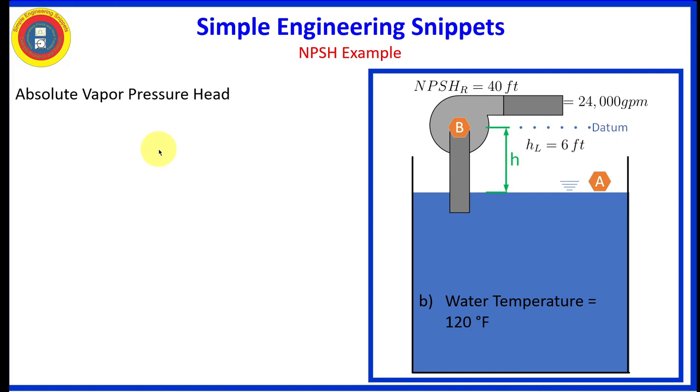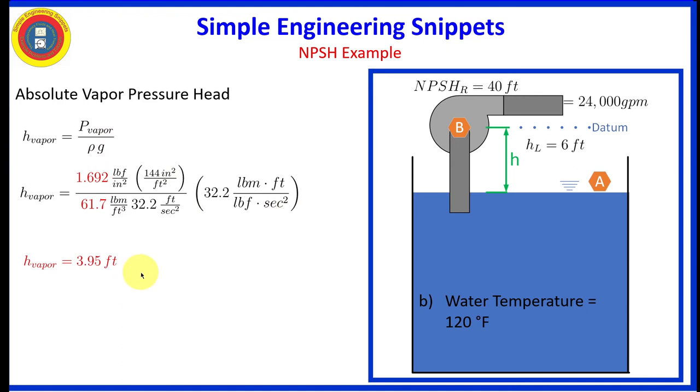Okay, going back in a little bit different direction. Let's calculate the absolute vapor pressure head first. And again, it's the vapor pressure divided by rho G. And it's the same calculation. Except now we get 3.95 feet. At 60 degrees, we got 0.592 feet. So a little over 6.5 times greater than what it was at 60 degrees. So quite significant.